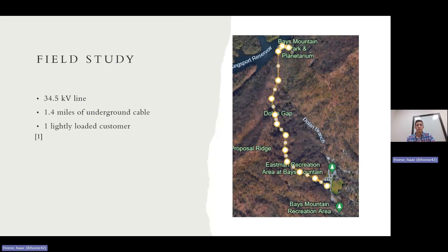So here's a field study that happened in the Kingsport, Tennessee area. You can see this line is 34.5 kV, so it's above that 25 kV threshold where ferroresonance can start happening. 1.4 miles of underground cable, so a lot of capacitance on this line. And it's only one lightly loaded customer on the top of mountain.